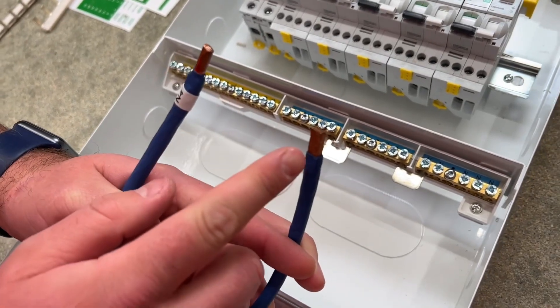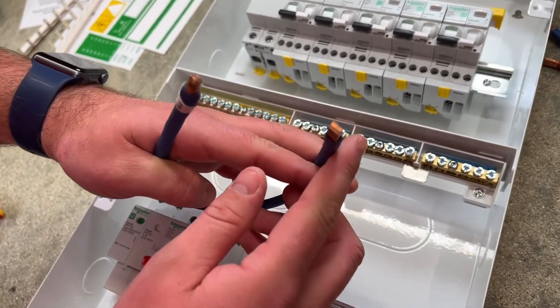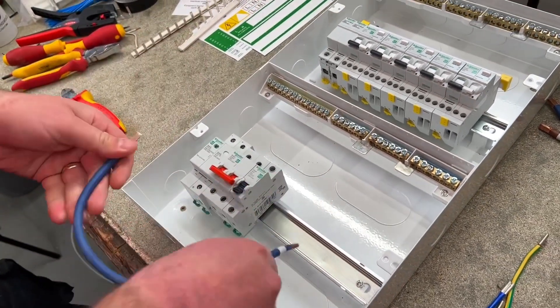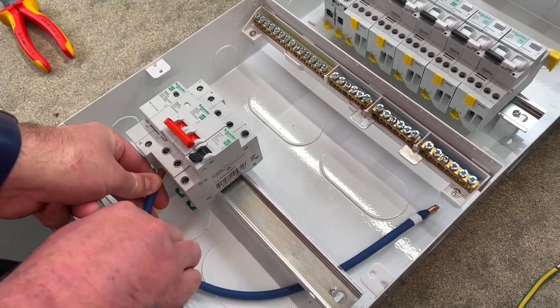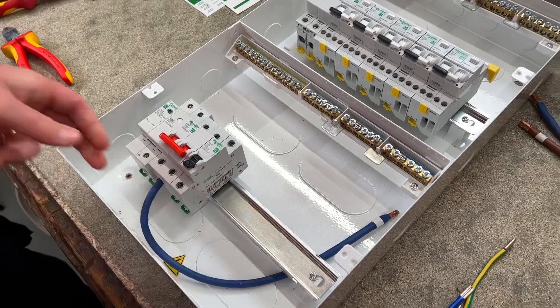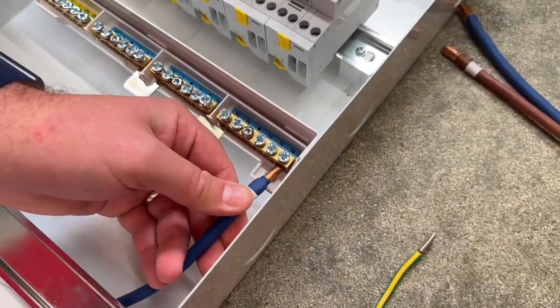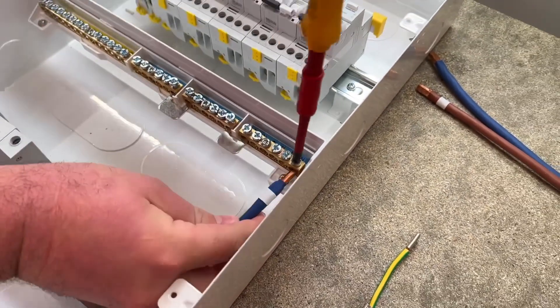Now all our components are in place, we can start putting the links in. This is the neutral link from the bottom of the double-pole switch to the neutral bar, and it's important you get these in the right way around — the rounded end goes into the neutral bar and the flat rectangular end goes into the double-pole isolator. That double-pole switch is not polarised, so there is no line and neutral label on it because it can go on the left or the right-hand side of the board, swapping position depending on where you install it.